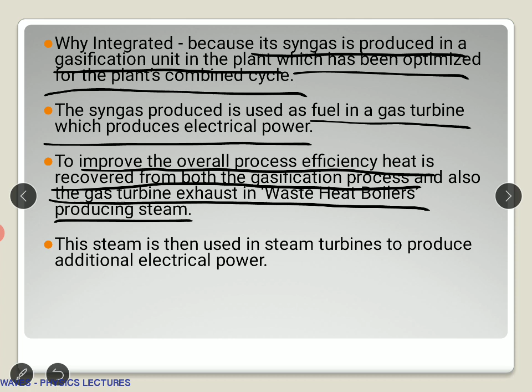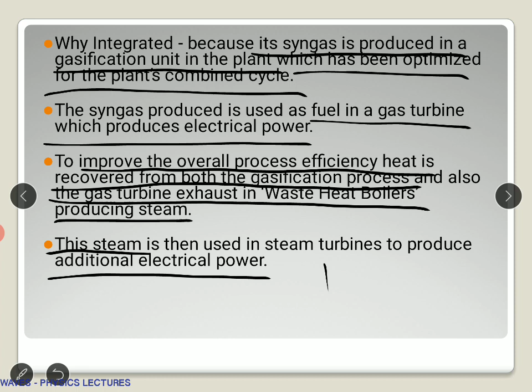What this does is improve the overall efficiency. Heat is recovered from both the gasification process and the gas turbine exhaust in waste heat boilers producing steam. So the heat which is actually wasted is recovered and used again. When this heat in the form of steam can be reused, we can generate additional electric power. We integrate a lot of things together so that we can improve the efficiency of the power plant.